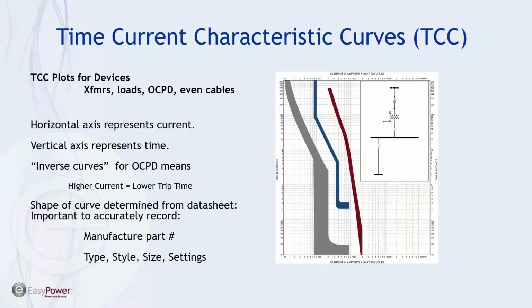Well, the tool that we use to verify this and to make this adjustment or recommendations is called the time current characteristic curve. And this mechanism has been around since the early days of switches and breakers, and it is used and specified for devices such as transformers, loads, overcurrent protective devices, and even cables. And what it does is allow us to predict safe operation and potential areas of damage by comparing the short circuit current or even the operating current in a particular load to the upstream devices. Now, it's not all that magical.